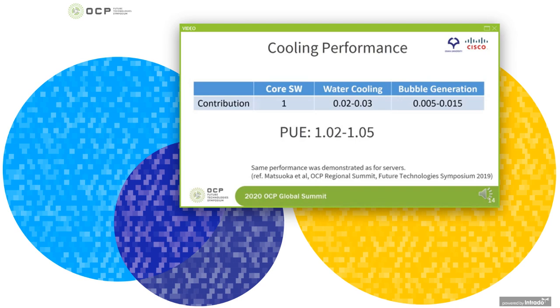Last but not least, let me emphasize that the bubble-assisted natural convection method achieved a PUE of around 1.02, which is the same as the result obtained for servers. In this system, using the free cooling method for heat exchange keeps the contribution of heat exchange and bubble generation significantly low, about 0.02. Therefore, by eliminating the need to air condition the entire data center, further reduction in power consumption can be expected.